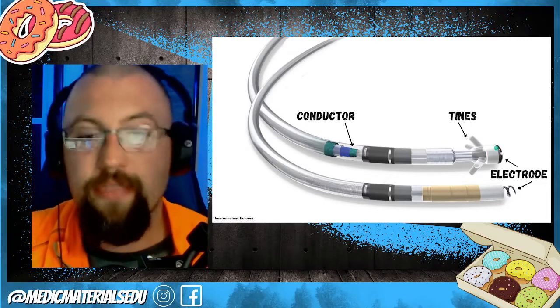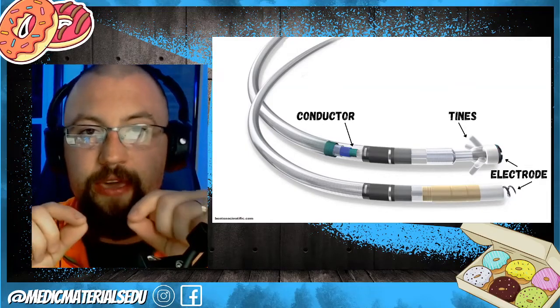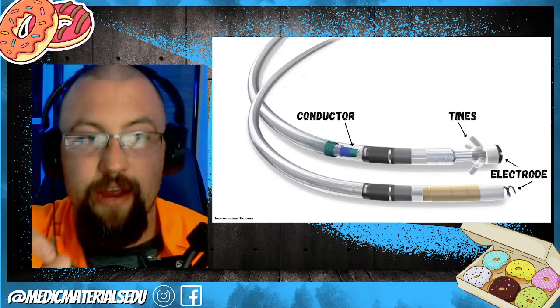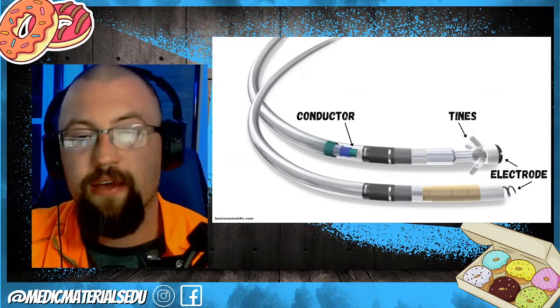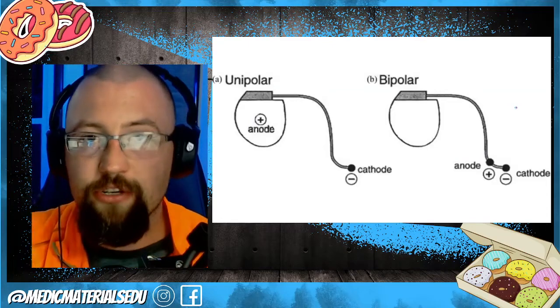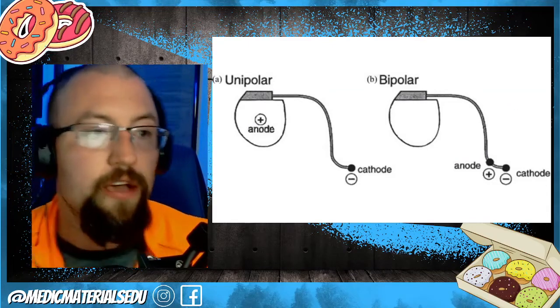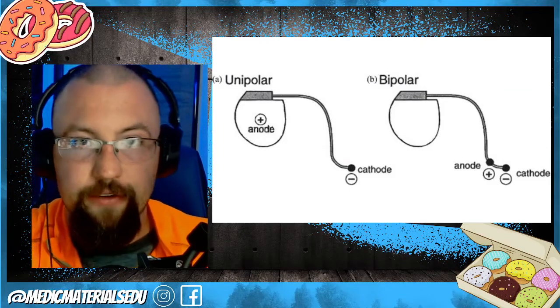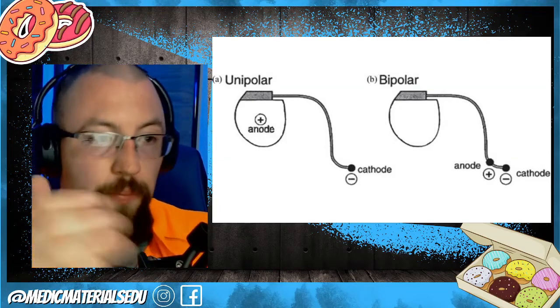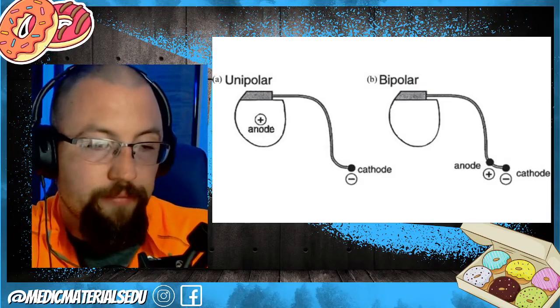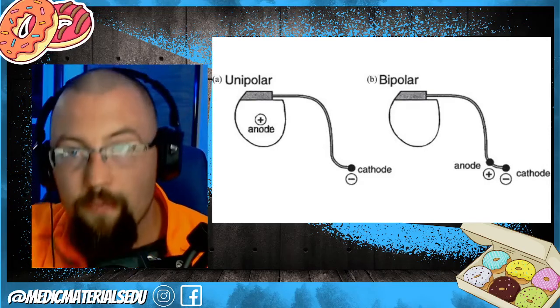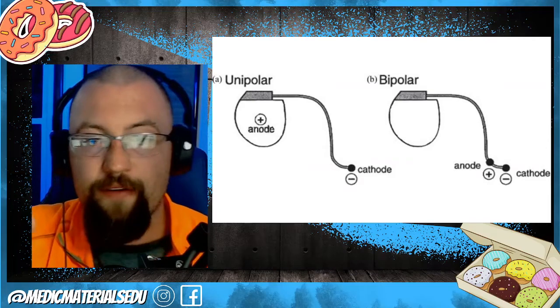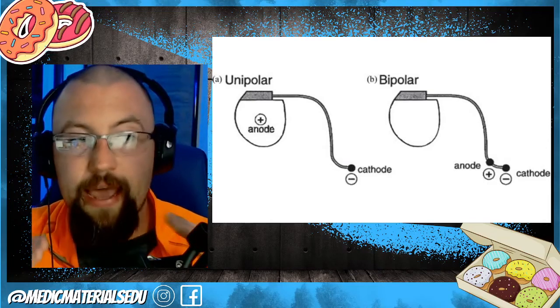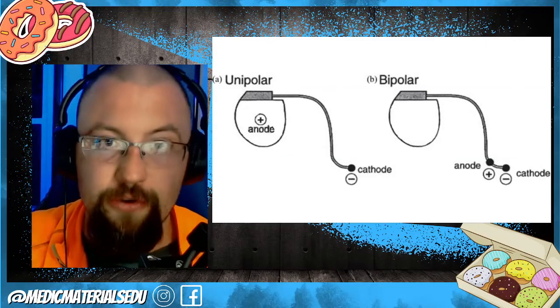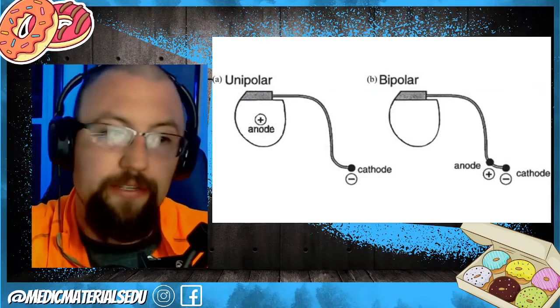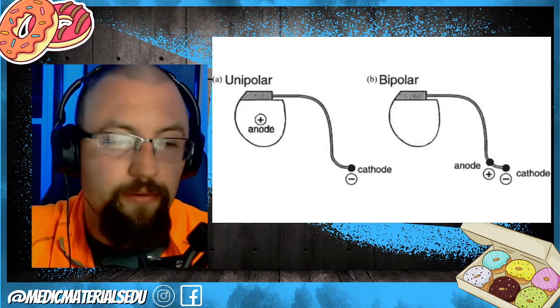All right. But this bottom electrode is still touching the myocardium, and this is where the pulse is actually generated from. So it comes down the conductor, it hits the electrode, and it provides the shock into the myocardium muscle. Now, because this is an electrical circuit, you need a circular flow of electricity. So there's unipolar and there's bipolar. Unipolar, we have the positive, which is where the pulse is generated, right? So the pulse is generated at the IPG, the pulse generator, and then it's moved down to the negative, and that's where you have the unload of the electricity. Then it has to go back through all of the chest tissue to get back to the positive piece in the unipolar pacemaker.